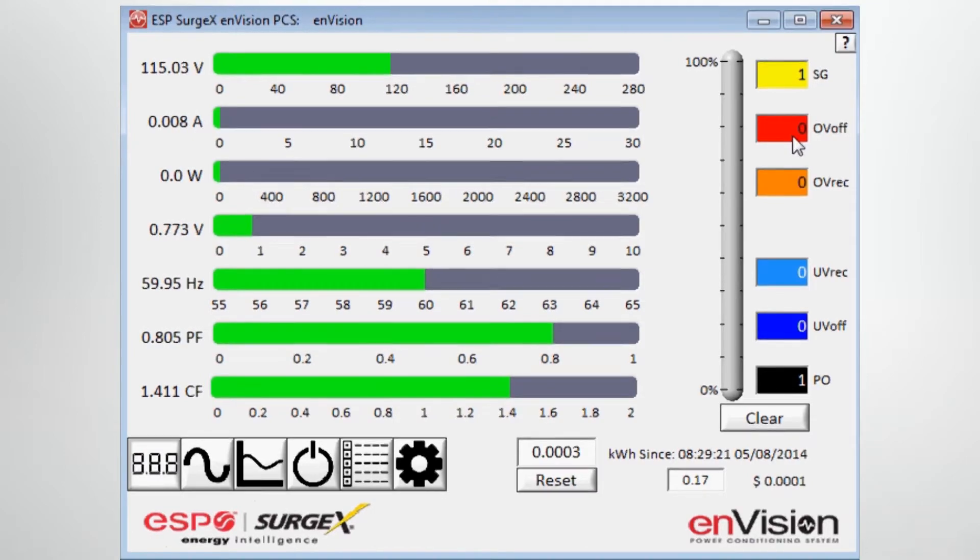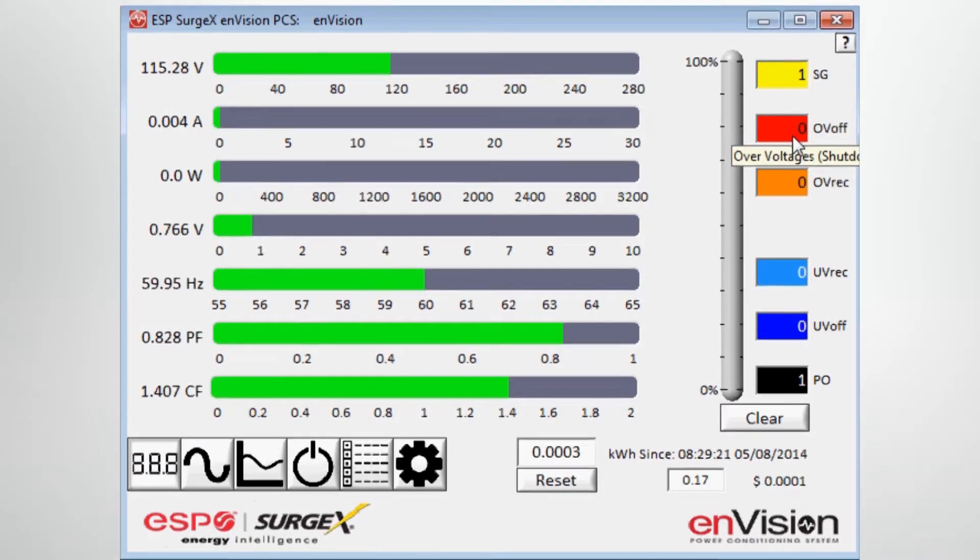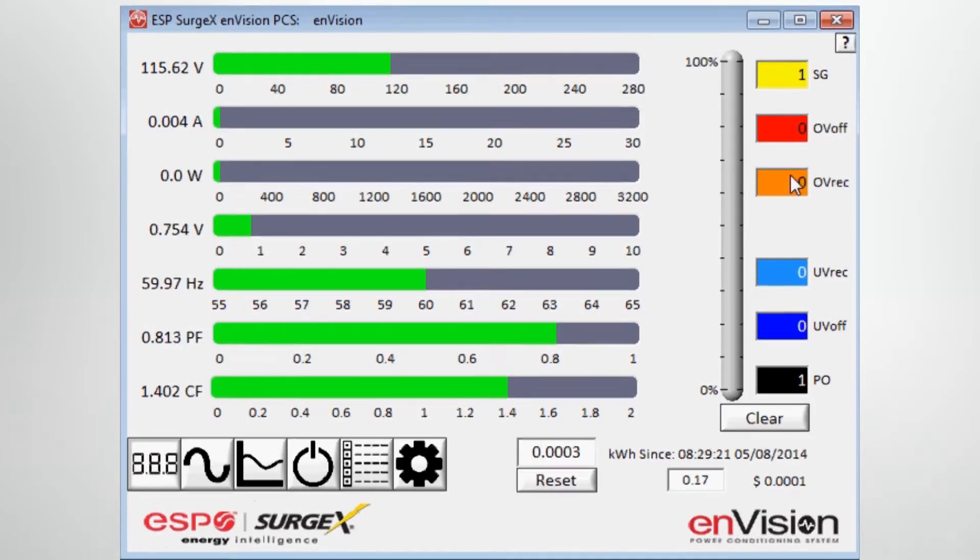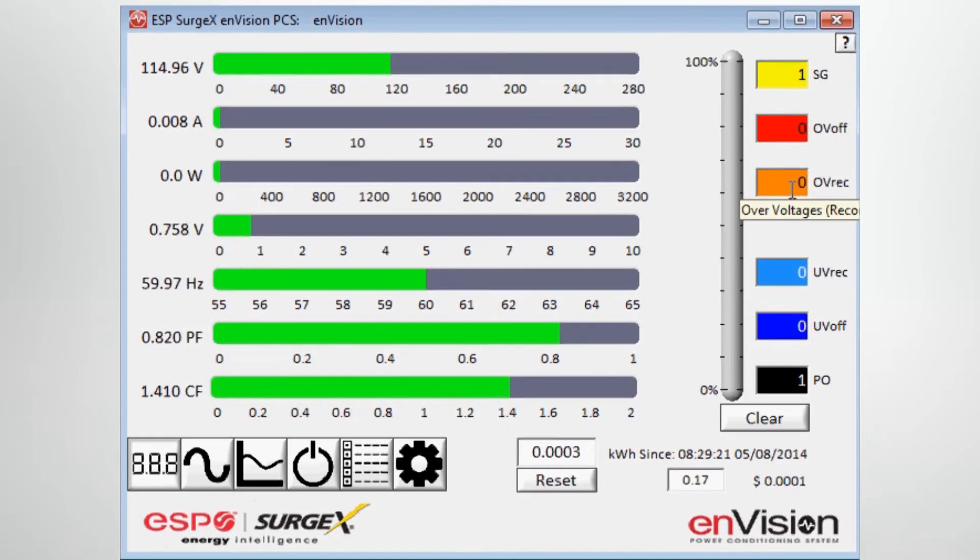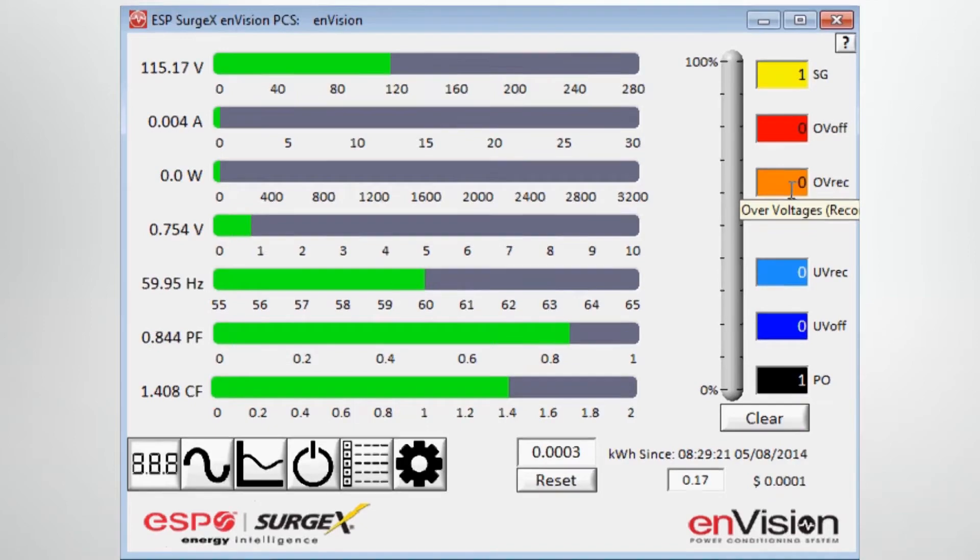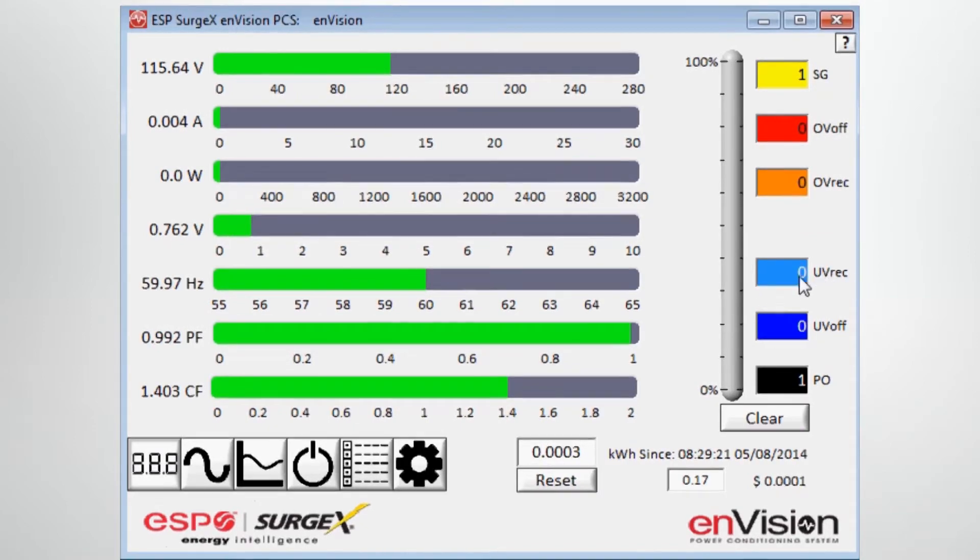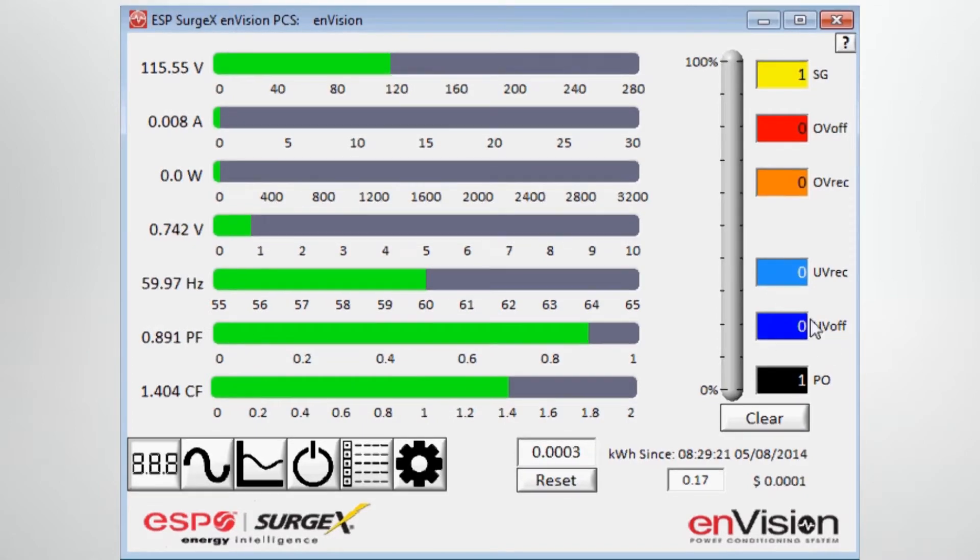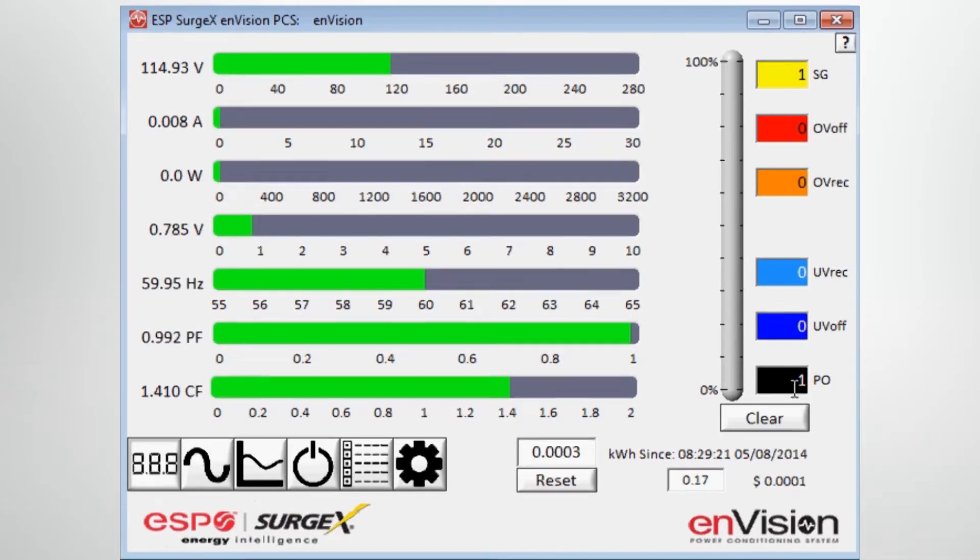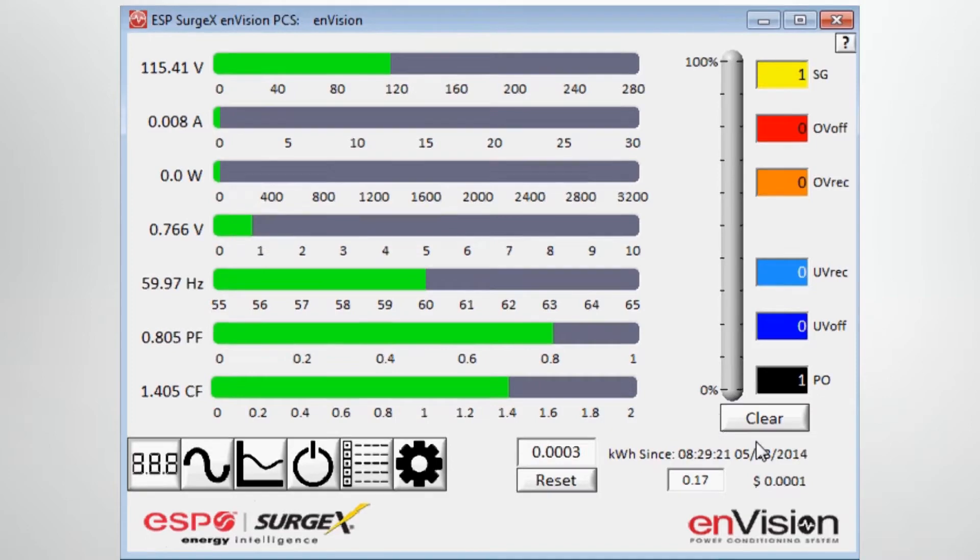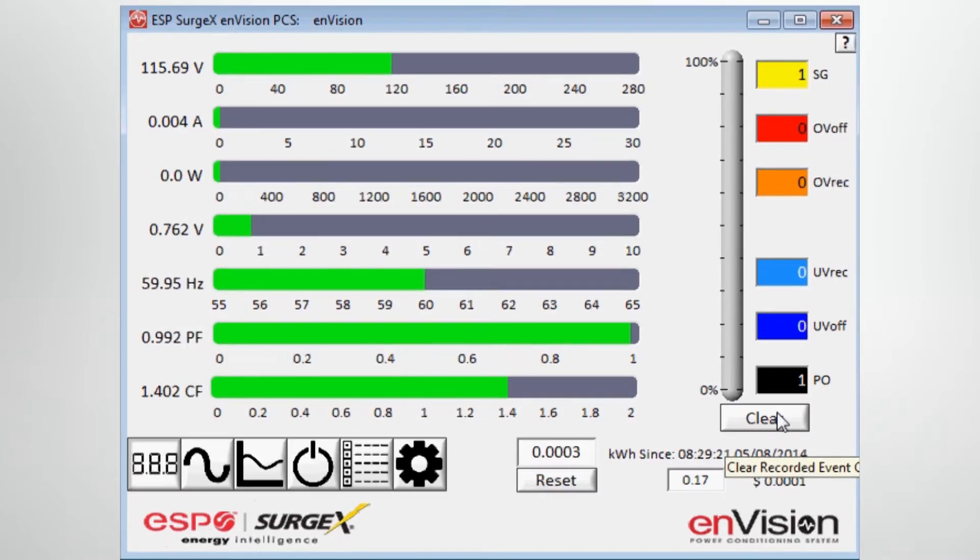The number of over voltage events that actually triggered a shutdown based on the user defined setting, the number of over voltage events that were triggered based on a record level but not necessarily a shutdown level, also user defined, and the same holding true for under voltage events, both recorded and those events that actually turn the unit off based on the user defined threshold. And then finally at the bottom, the number of power outage events that occurred. You have the ability to clear those events with the push of a button.